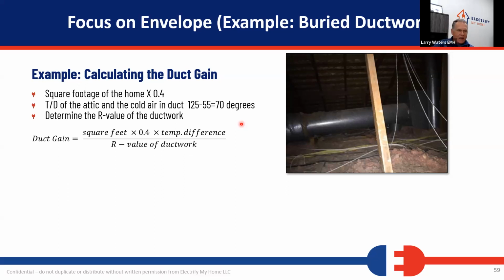If we look at the average, a BPI standard, Building Performance Institute standard, is internal surface area of the ductwork equals between 0.38 and 0.42 of the square footage of the house. So in other words, if I have a 1,000 square foot house, we look at it as there's about 400 square feet of internal duct surface area in that house. And if it's all in the attic, we can calculate this really easily.